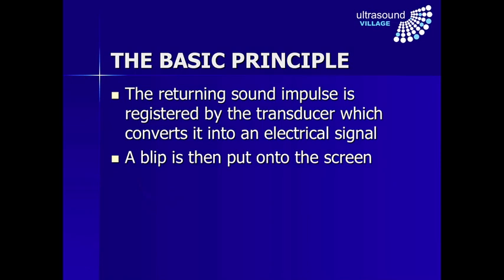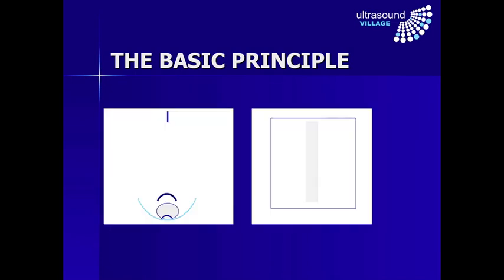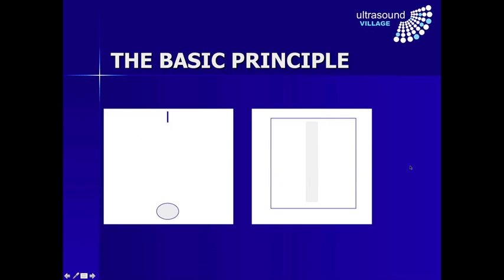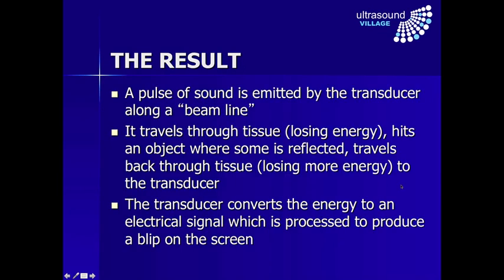The returning sound pulse hits the transducer, is converted into an electrical signal, sent to the machine, the machine processes that and puts a blip onto the screen. So we have the original pulse emitted, a reflection from the front of the object, a reflection from the back of the object — they travel back towards the transducer. When the first returning signal hits the transducer the machine puts a blip on the screen; a moment later the second returning impulse hits and the machine puts a second blip on the screen.